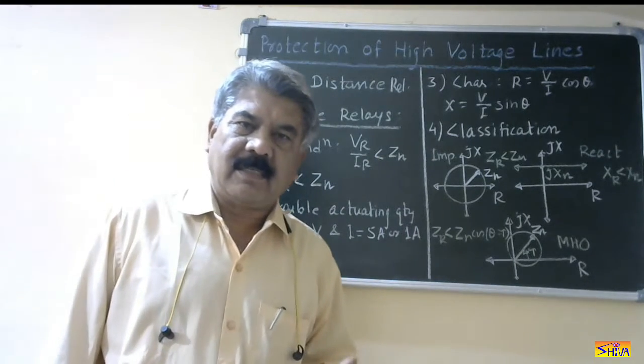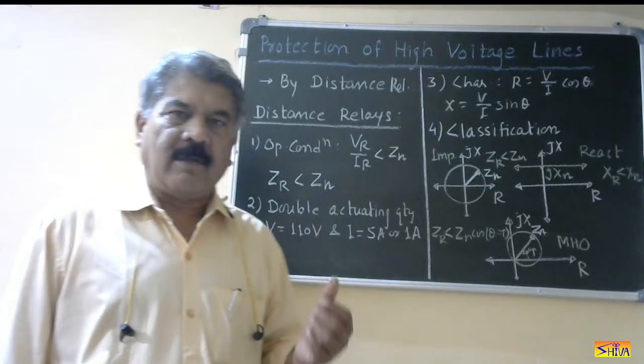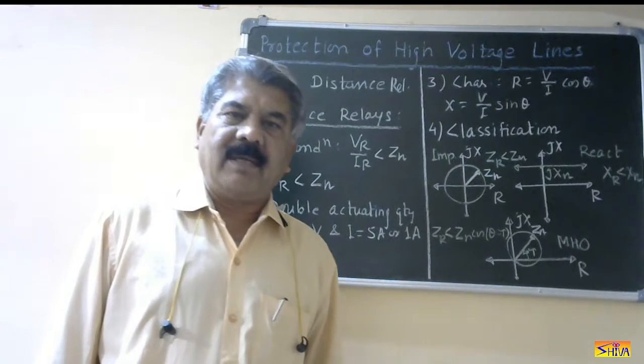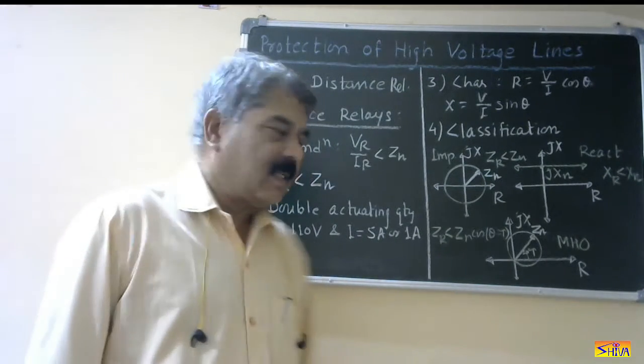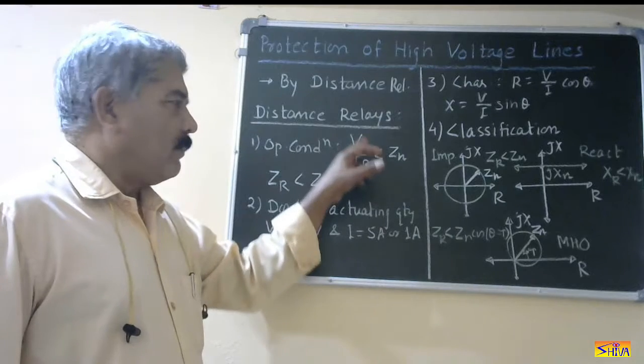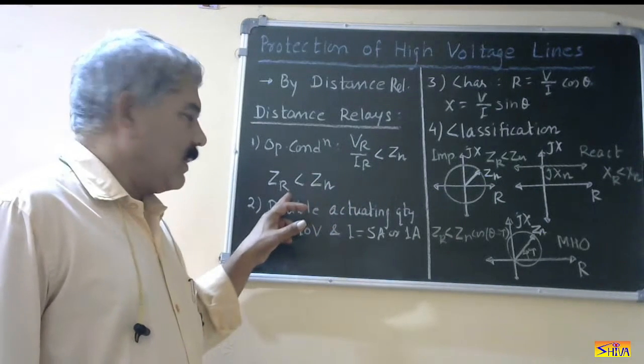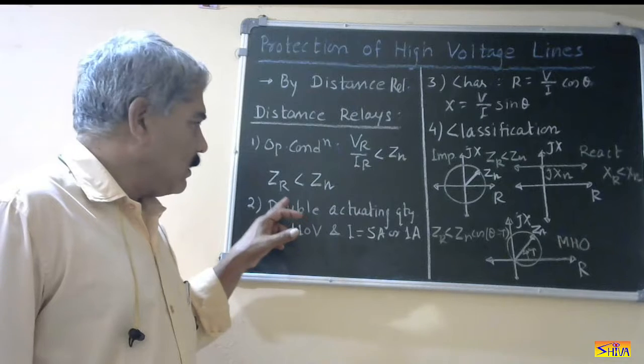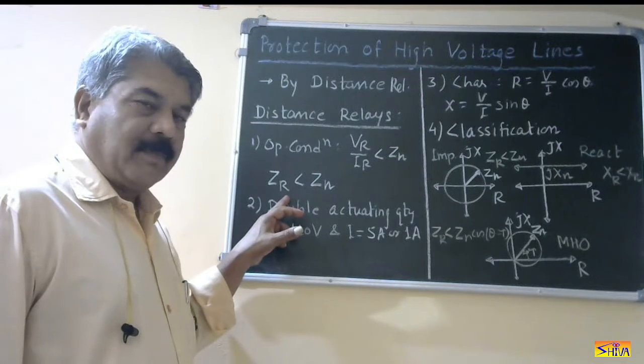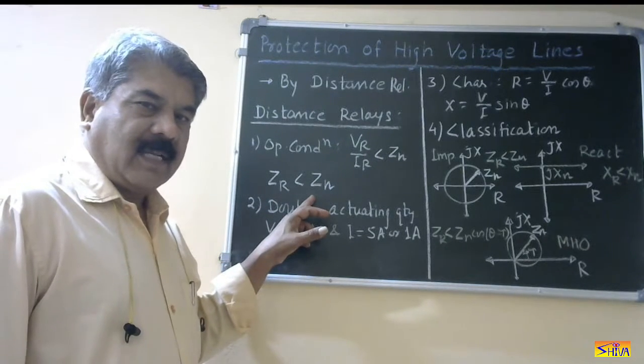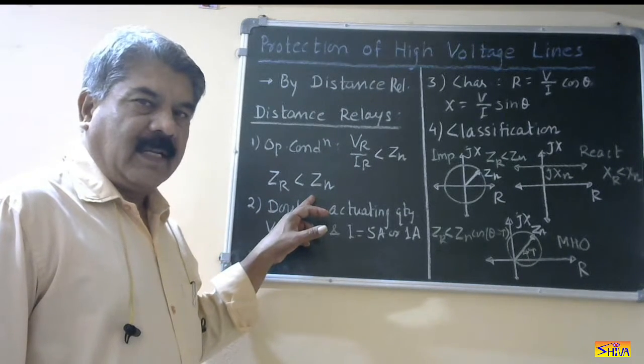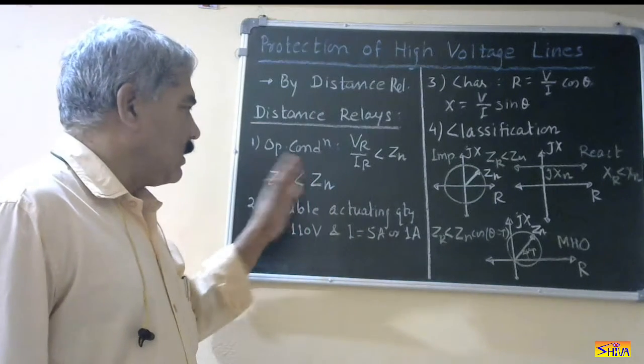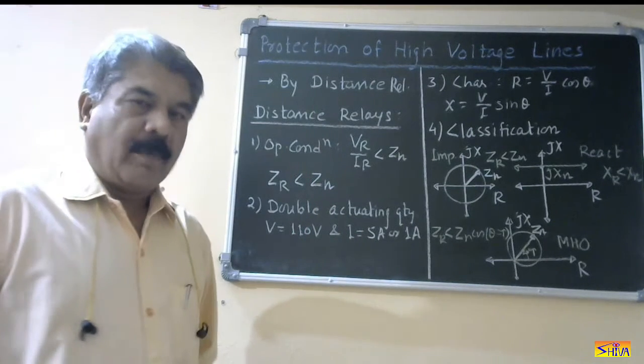This impedance is nothing but the measure of distance of the fault from the relay location. Therefore, the generic name is distance relays. Vr upon Ir we can write in terms of impedance, so that is Zr — the impedance measured by the relay. If it is less than the impedance setting of the relay Zn, then the relay operates. So this is the operating condition.